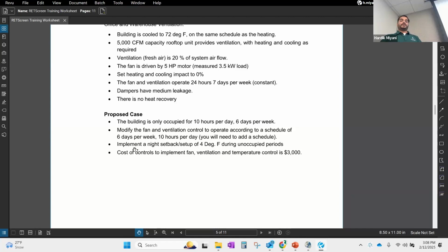The second measure that we are implementing here is a nighttime setback. Usually during occupied hours, the building has a set point of 68 and 72. But when there is no one in the space, why should I maintain 68 and 72°F, right? I could potentially make it 60 for heating and 80 for cooling. So I'm saving energy there. I am not letting my system turn on when there is no one in the building. So that is the nighttime setback, which means during nighttime I want my temperature to go on a safer side, to conserve energy. They have asked for a 4 degree dead band for that.